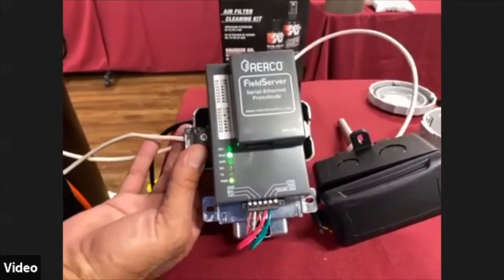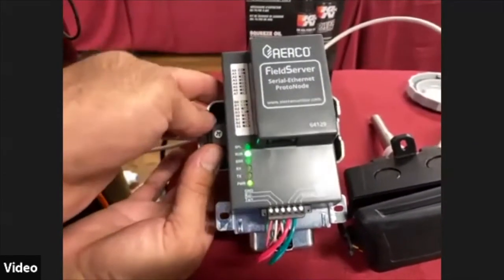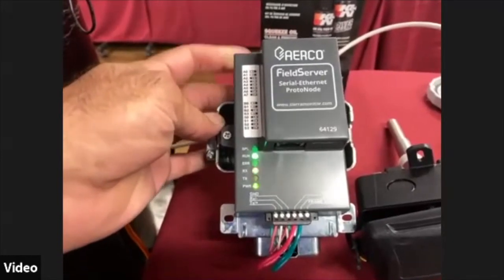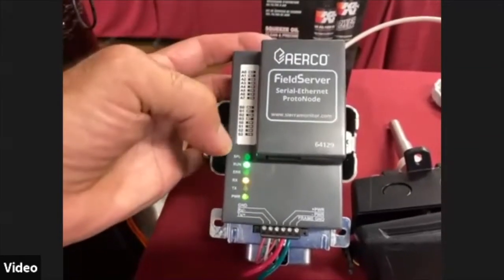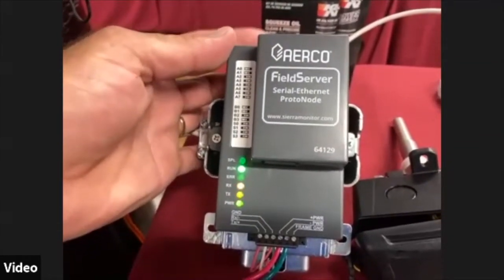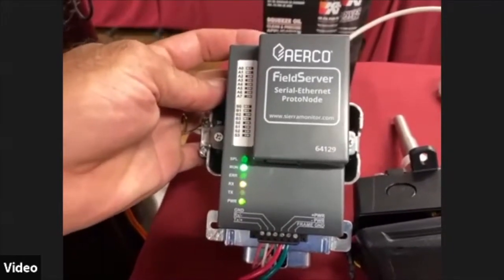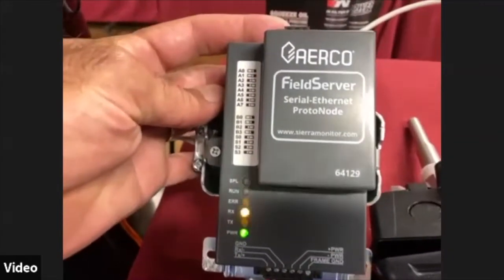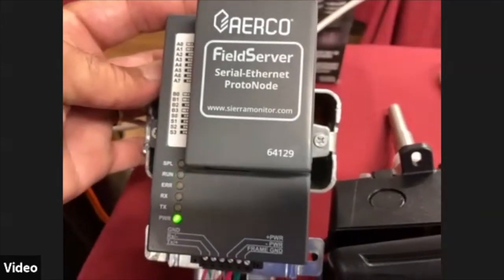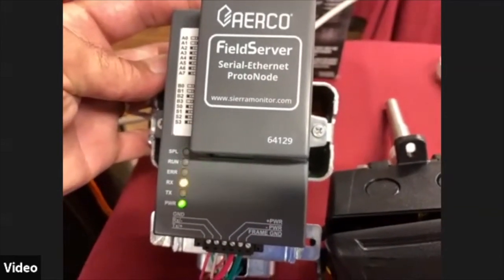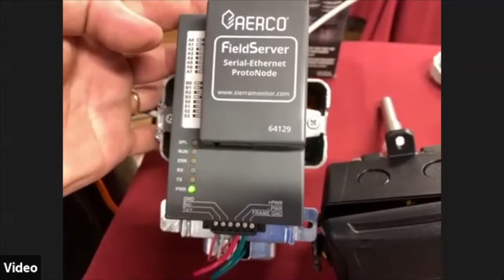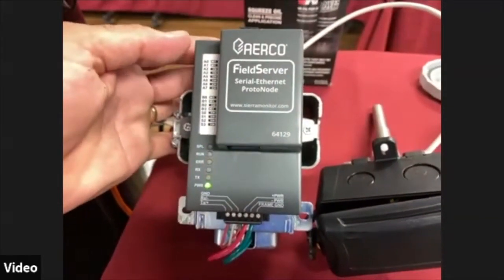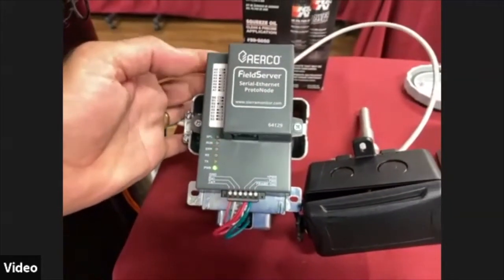So this allows us, if it's set correctly, if all of our variables are set correctly in here, to communicate with the building management system in BACnet IP or BACnet MSTP. If it was LonWorks, we can do that as well. Different gateway, just be aware of that. It won't communicate with the same gateway.